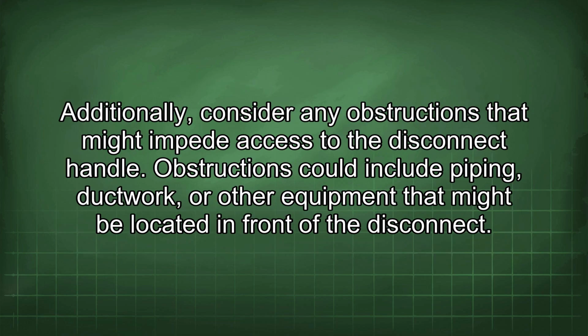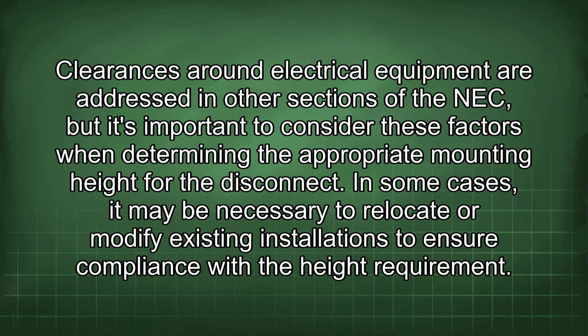Additionally, consider any obstructions that might impede access to the disconnect handle. Obstructions could include piping, ductwork, or other equipment that might be located in front of the disconnect. Clearances around electrical equipment are addressed in other sections of the NEC, but it's important to consider these factors when determining the appropriate mounting height for the disconnect.